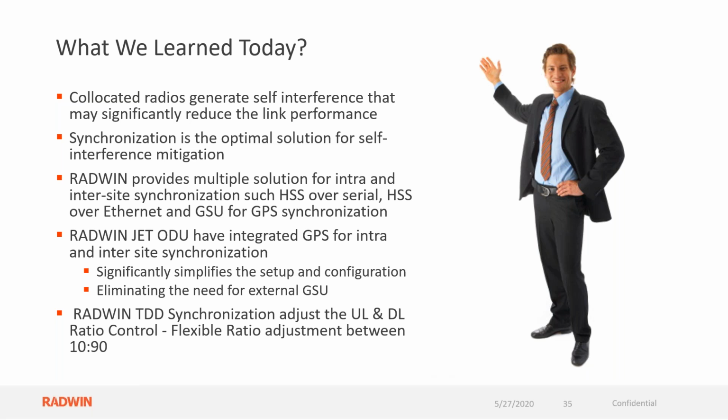And when you shift the phase, it can damage or impact the uplink downlink ratio from different entities towards the control center. This is something that needs to be considered carefully when you are deploying and adding a GSU for inter-synchronization.